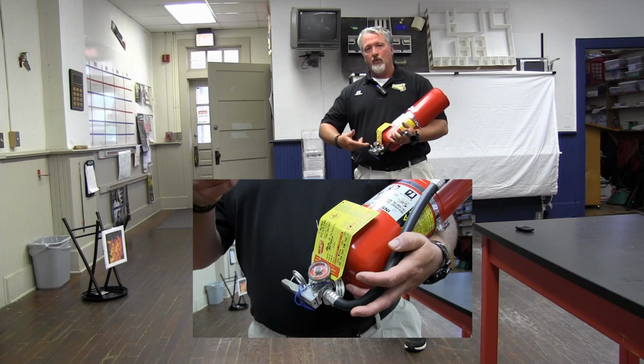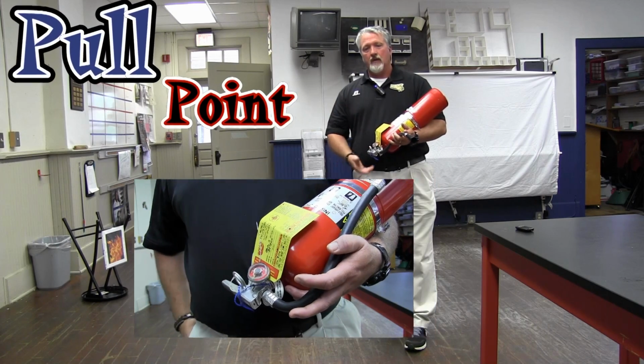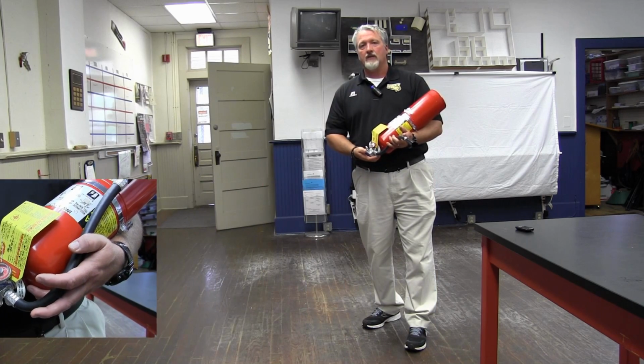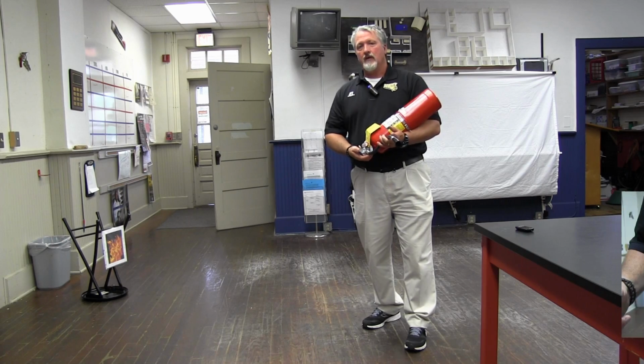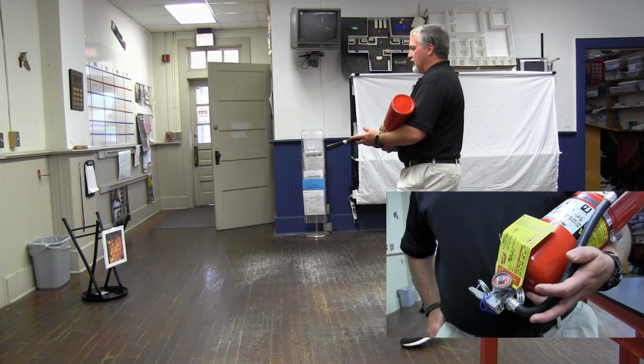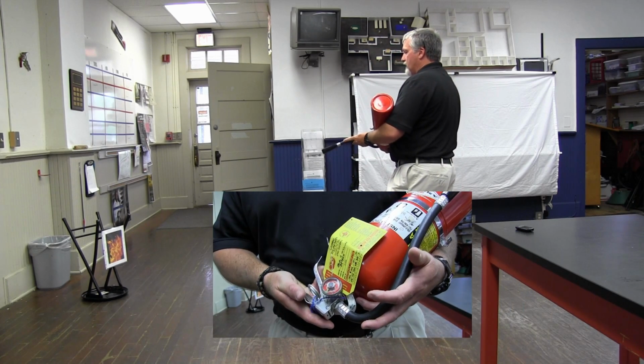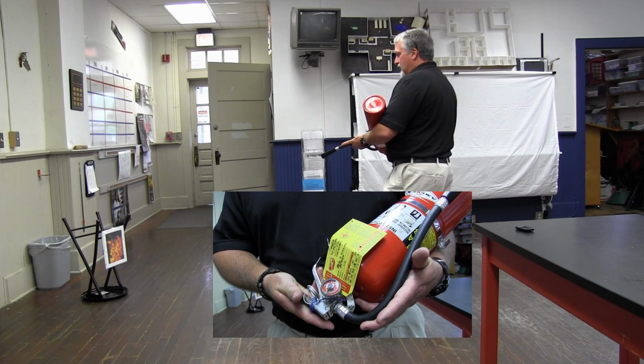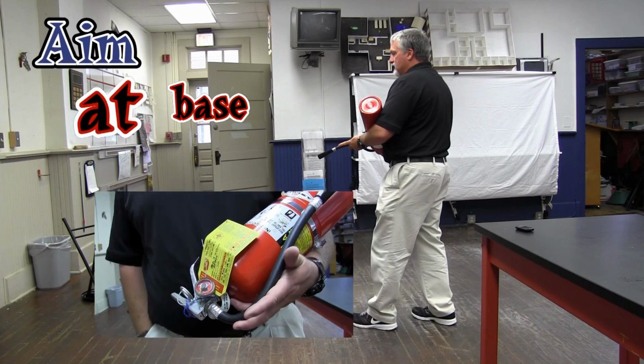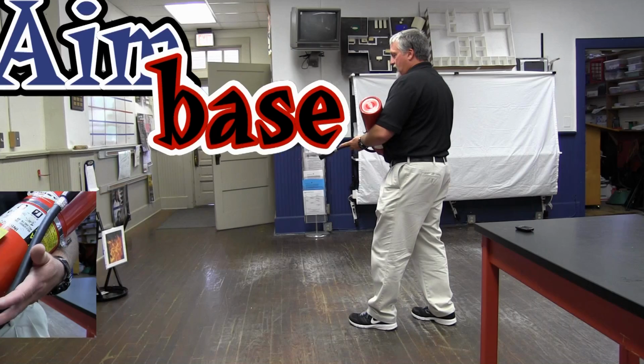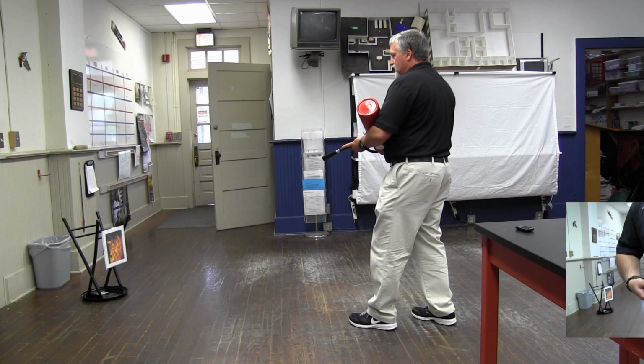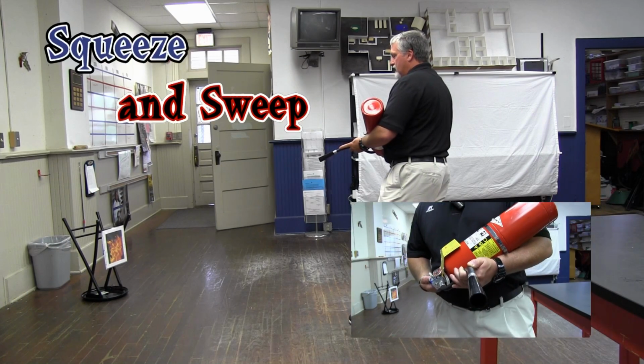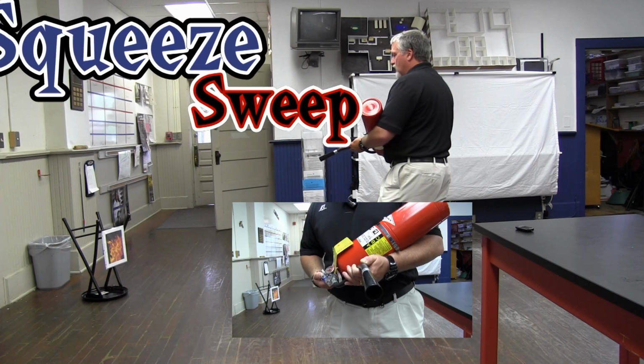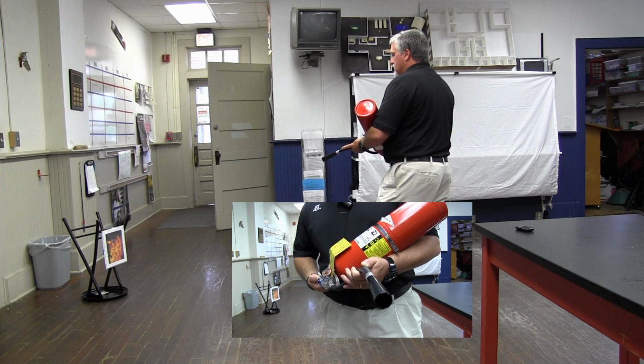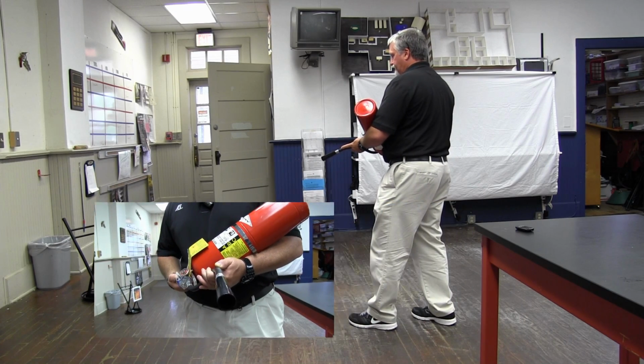You would pull this pin and squeeze these two paddles together. Then, as I said, staying a safe distance from the fire, you will point or aim at the base of the fire, the source of the fire, and you will slowly sweep the head of your fire extinguisher across the base, extinguishing the fire.